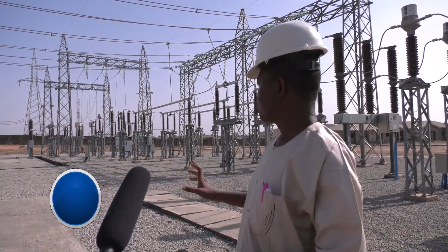More especially the Zuru side - they propose 132 kV at Zuru. So the 132 kV that is coming in, then we have the transformer bay, where we have 2 by 40 MVA transformer. The T1, that is a 40 MVA transformer, is already in circuit almost for 2 years now. So now the second transformer, the work is in progress, almost 60% finishing on the transformer. Then the feeders, the work is still in progress.